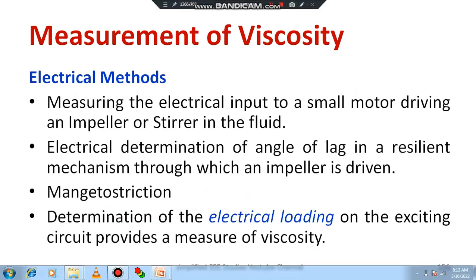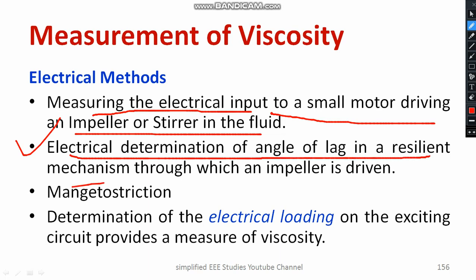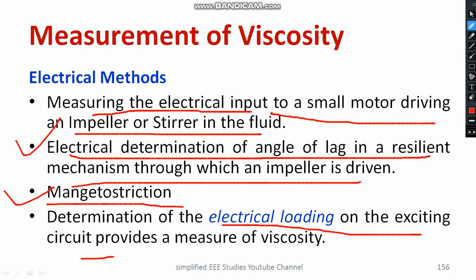There are also a few electrical methods for measuring viscosity. One involves measuring the electrical input to a small motor driving an impeller stirring the fluid. Another is the electrical determination of the angle of lag in a resilient mechanism through which the impeller is driven — the impeller is coupled with the motor. A further method involves magnetostriction, which will be covered in a separate topic. Additionally, there is determination of electrical loading on exciting the circuit provided for measuring viscosity.